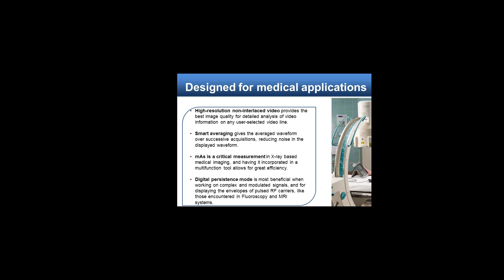Smart averaging reduces the noise on the waveforms, and the mAs measurement improves efficiency in the X-ray based medical imaging measurements by showing the X-ray tube current and then easily being able to also show the kV waveforms. Digital persistence mode is for those really complex modulated signals, and this is important for pulsed RF carriers like those that you'll encounter in fluoroscopy or MR systems. Its complete functionality makes the 190M the right tool to use for troubleshooting.